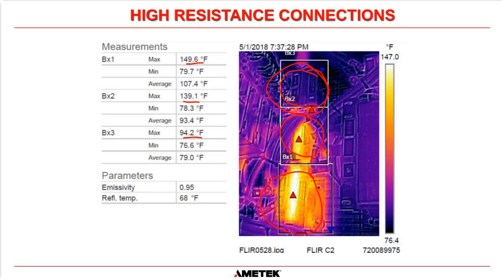And what we found was there was a mistake made in the connections of these chokes, either by the factory or, I think it was actually when you had to connect two systems together, two panels, because it was a large system, and the wrong cable was landed on the wrong place, which basically bypassed this choke altogether. And that was only found because we did a thermal scan on that system. So once again, by using an infrared camera, you can find things that you won't be able to find with the visible eye, should I say. Okay.